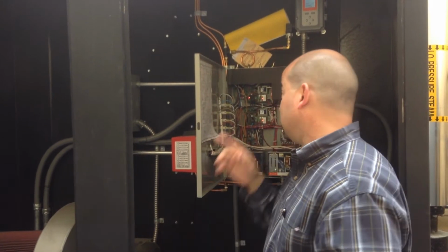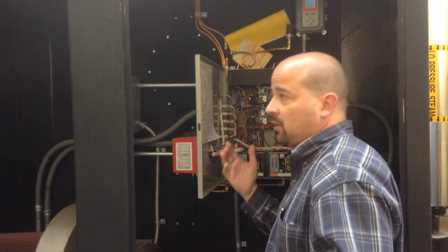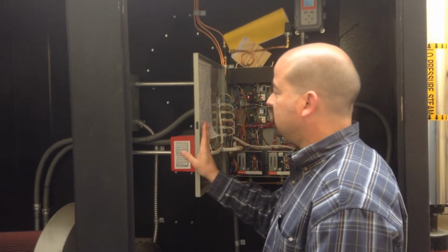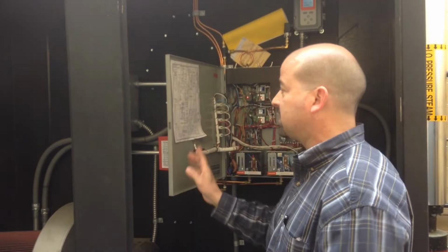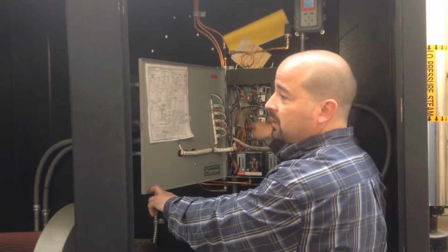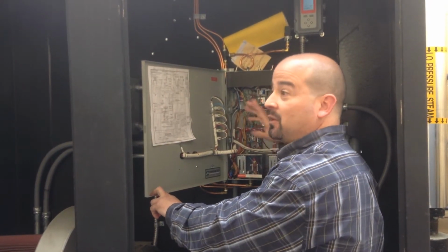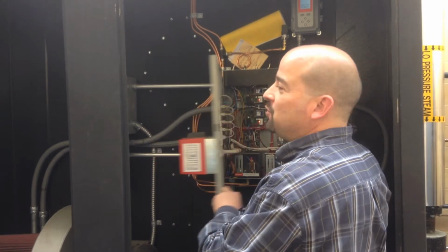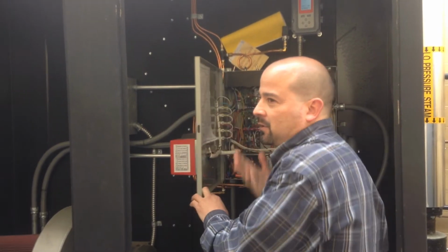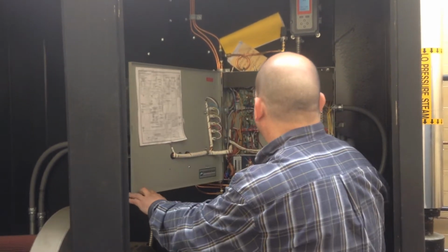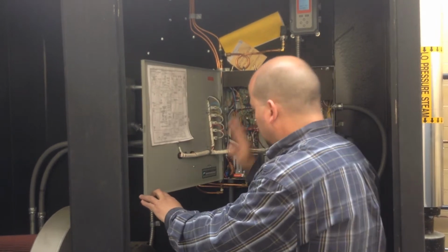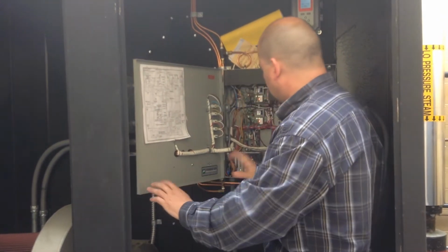If you say, hey, I think I have a problem with one of these boards because it's going off on low water cutoff, then I'll say leave it open for 24 hours, whatever. Next time it goes on alarm, walk up to it, tell me what LEDs are on and what are not. Then we know where to go. But if you cycle the power, it's going to start all over again and you won't know. Yeah. So I'll go through the panel.